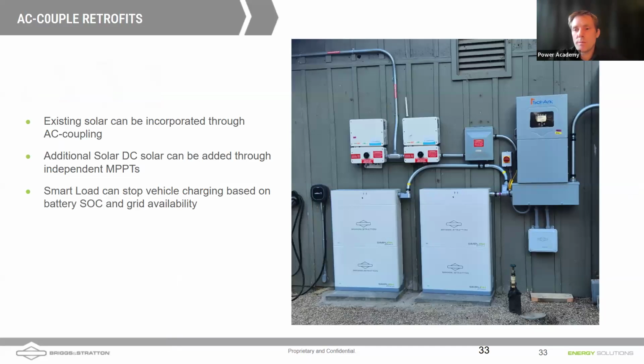Here's an example of an AC coupled system that does not have a generator attached. Maybe a slightly simpler example. Commonly, we see these SolarEdge grid tied inverters that don't have the ability to add batteries, right? Or we might also see an Enphase grid tied system on the roof, as was shown in the previous example with microinverters. If you do want to have backup and you have a system like that, we can do what we call a retrofit. Here we're looking at an example where the power coming down from your solar goes into these grid-tied inverters. And then we've got the output of these grid-tied inverters at 240 volts AC passing into the Sol-Ark inverter. The Sol-Ark inverter is using that power to power the loads in the house and charge up the batteries. In a grid down event, if we did not have the batteries, this system would provide no backup, right?